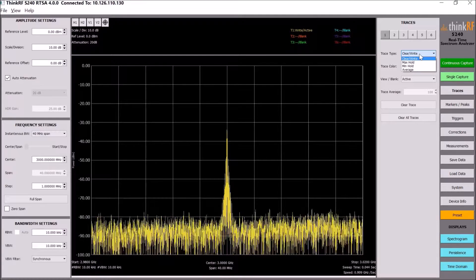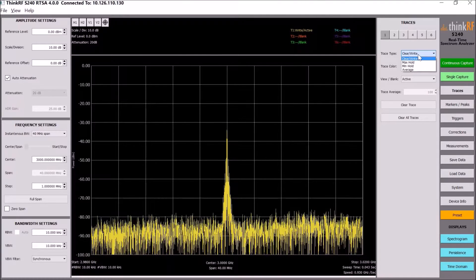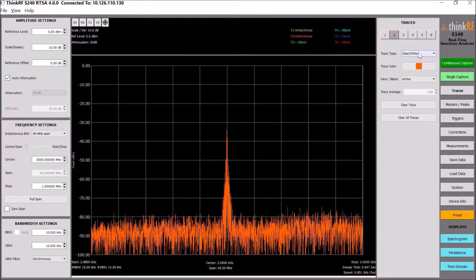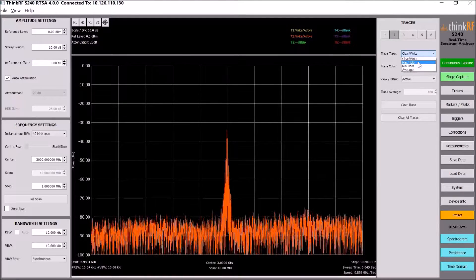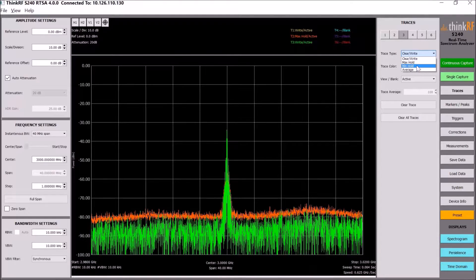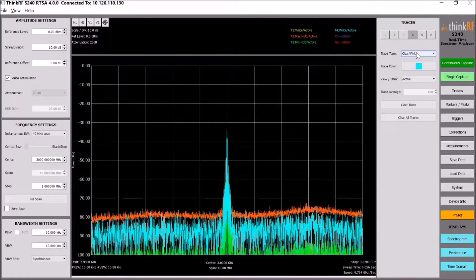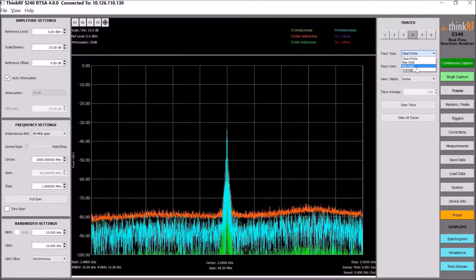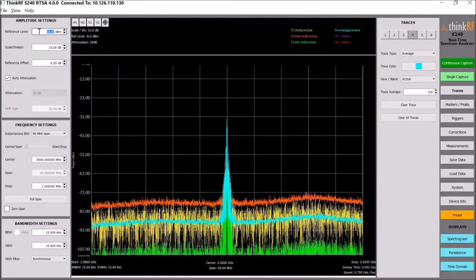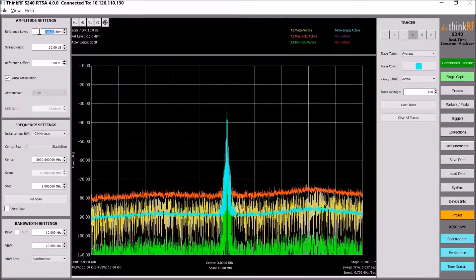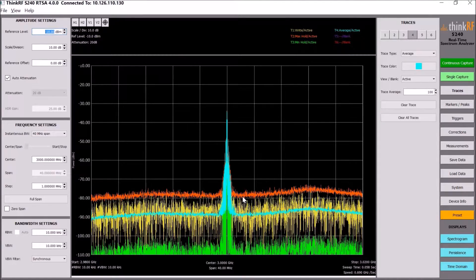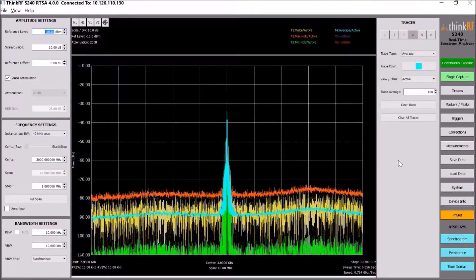The four trace types are: clear write, max hold, min hold, and average. You can assign a different type to each trace — for example, trace one can be clear write, trace two can be max hold, trace three min hold, and trace four average. You can see all of them simultaneously if you reduce the reference level.